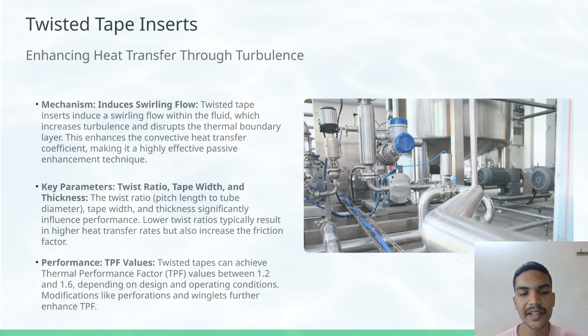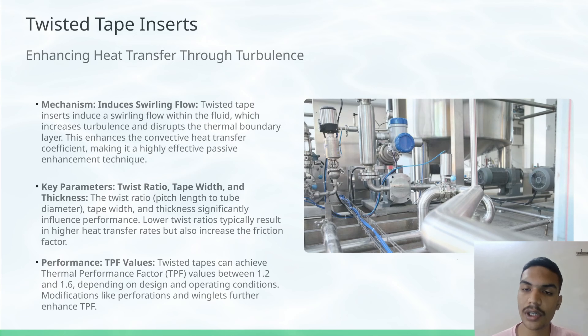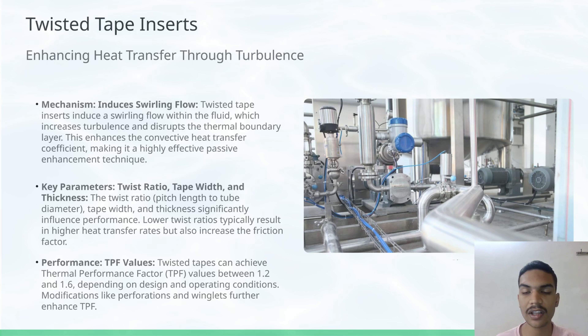the TPF value is generally between 1.2 and 1.6, depending on design and operating conditions. A high TPF denotes that the heat exchanger is good in thermal heat exchange, but simultaneously the pressure drop and friction factor will increase. A low TPF value denotes low heat transfer enhancement rate but also a lower pressure drop.